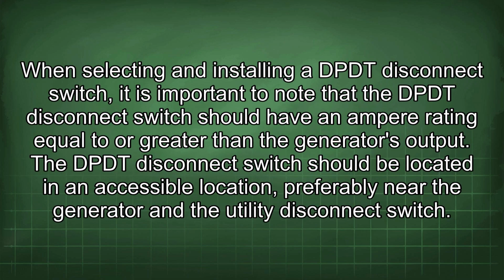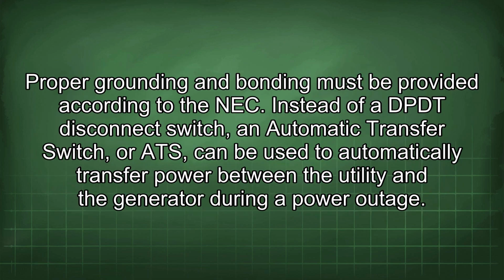When selecting and installing a DPDT disconnect switch, it is important to note that the DPDT disconnect switch should have an ampere rating equal to or greater than the generator's output. The DPDT disconnect switch should be located in an accessible location, preferably near the generator and the utility disconnect switch. Proper grounding and bonding must be provided according to the NEC.